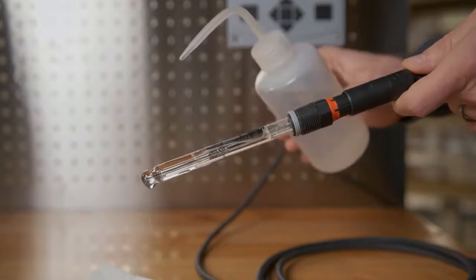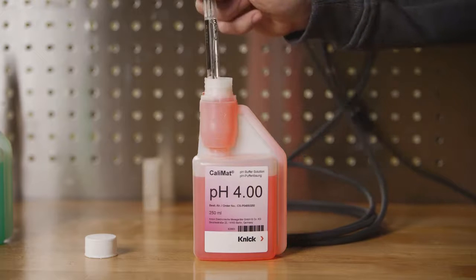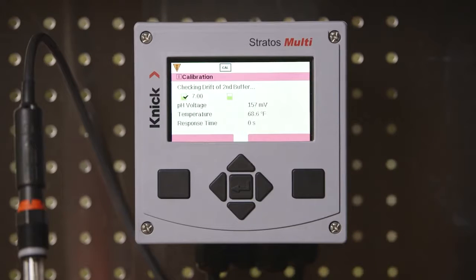We will do so and place our sensor in the buffer 4 solution. Again, stir lightly and press Next to proceed. As with the first step, you can see that the transmitter automatically recognizes the second buffer value, displays the pH voltage, temperature, and response time.